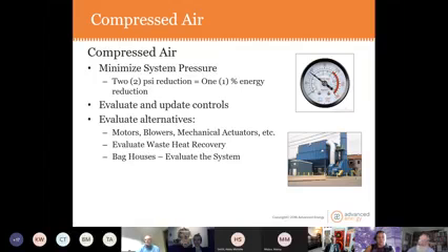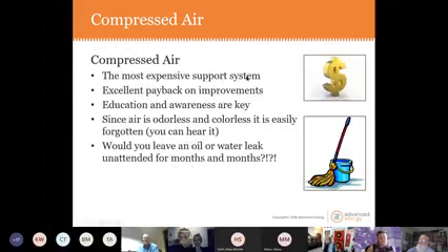Evaluate the waste heat recovery from compressors. It's not a lot. It's not like combustion from natural gas, but there are some things you can do with the waste heat from a compressor. Bag houses are big filter houses that filter out big processes like foundries or somebody that makes a lot of dust, textiles. They use a lot of compressed air. And if there's a bag house in a plant that you're looking at, you need to think about evaluating your bag house system. It's the most important expensive support system. That means the paybacks can be very good.